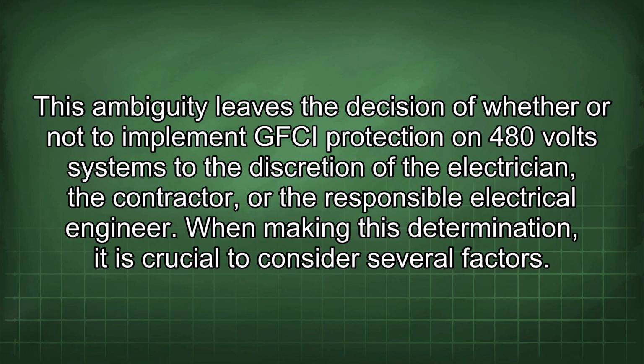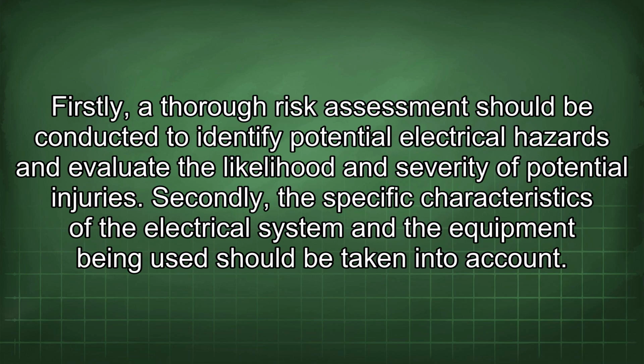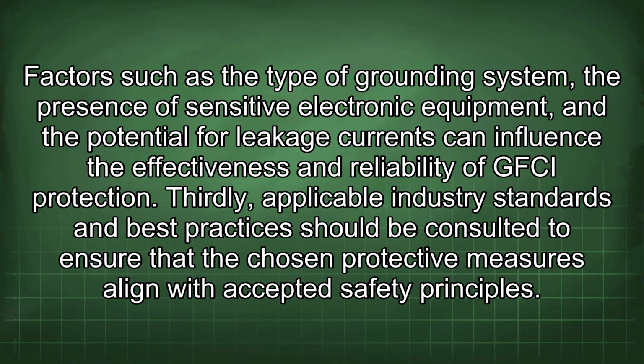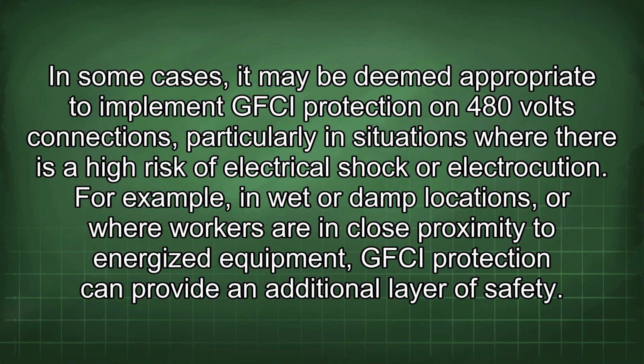When making this determination, it is crucial to consider several factors. Firstly, a thorough risk assessment should be conducted to identify potential electrical hazards and evaluate the likelihood and severity of potential injuries. Secondly, the specific characteristics of the electrical system and the equipment being used should be taken into account. Factors such as the type of grounding system, the presence of sensitive electronic equipment, and the potential for leakage currents can influence the effectiveness and reliability of GFCI protection. Thirdly, applicable industry standards and best practices should be consulted to ensure that the chosen protective measures align with accepted safety principles. In some cases, it may be deemed appropriate to implement GFCI protection on 480 volt connections, particularly in situations where there is a high risk of electrical shock or electrocution.